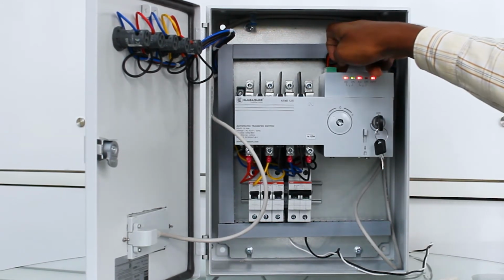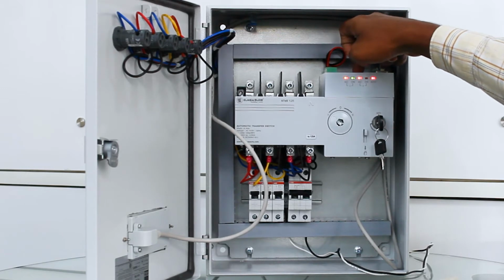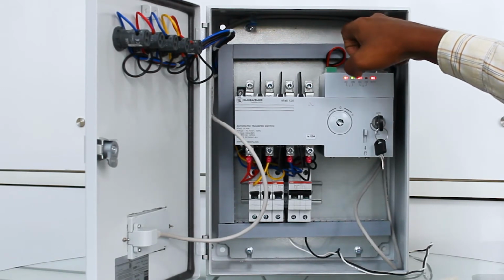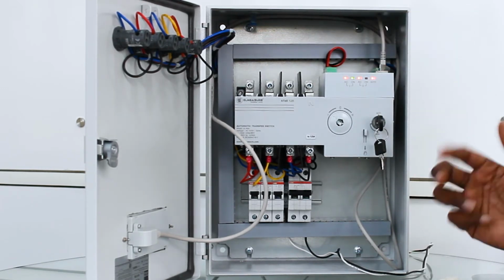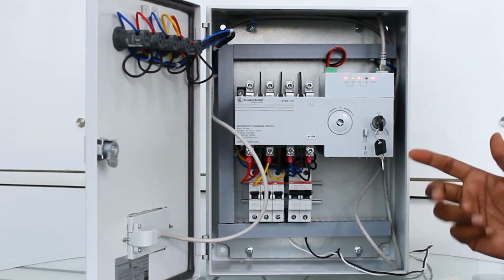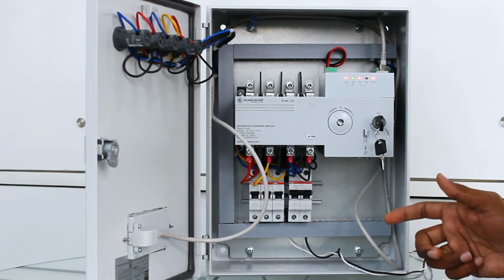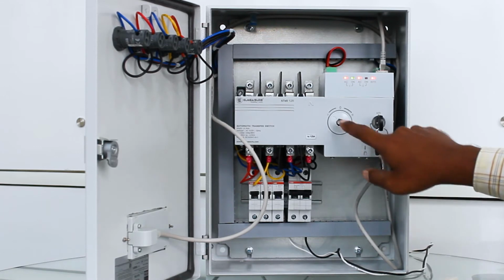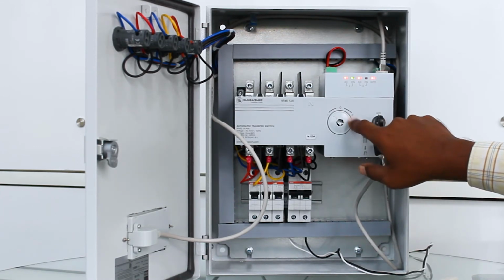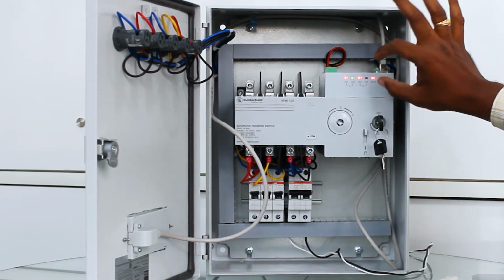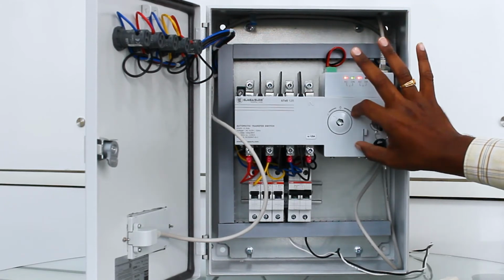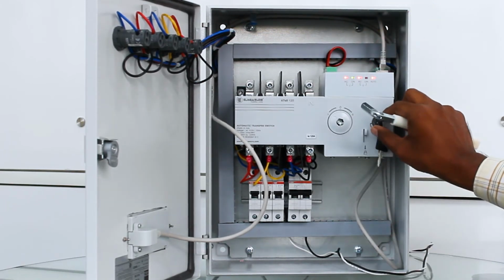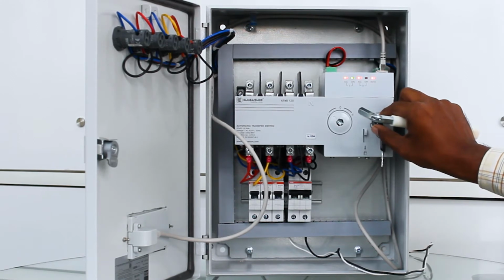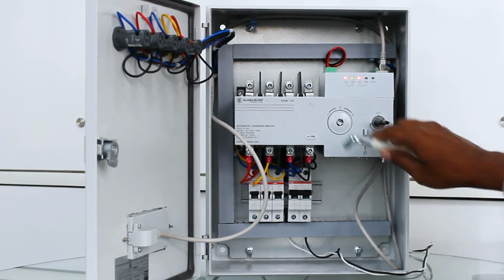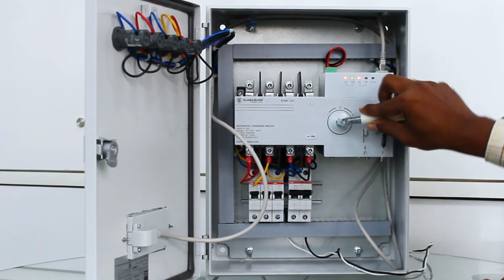We have one more option also. We have a few terminals on the top side of the controller for the remote mode of operation. Some customers want to control the device remotely, like PLC SCADA integration. That is also possible. And the third mode is by emergency handle. If any problem occurs in the controller part or motor part, we can change over manually. Before changing over manually, we need to put it in manual mode. Then we can change over from one source to another source.